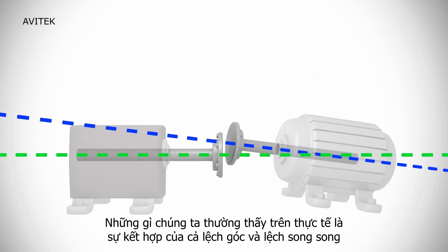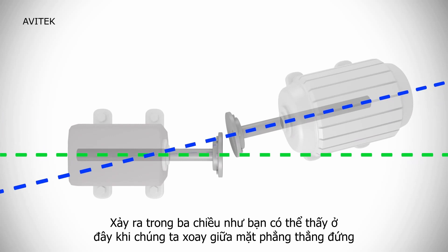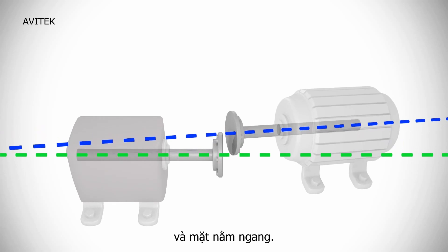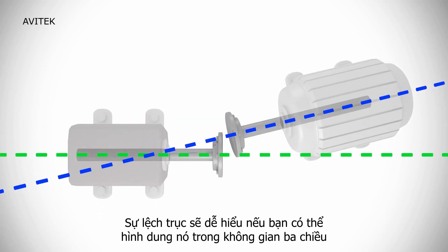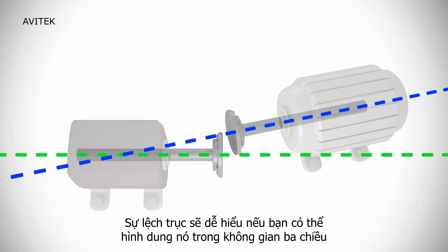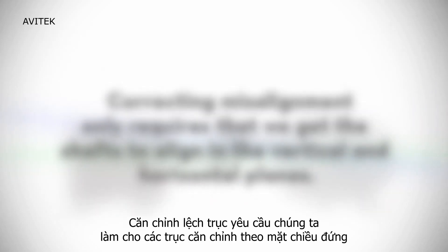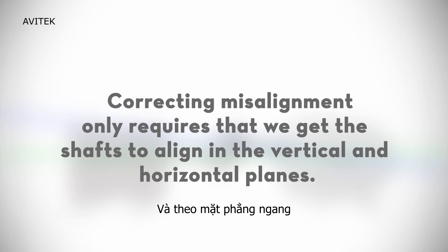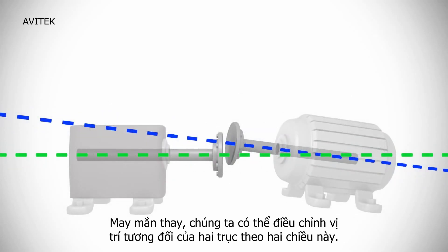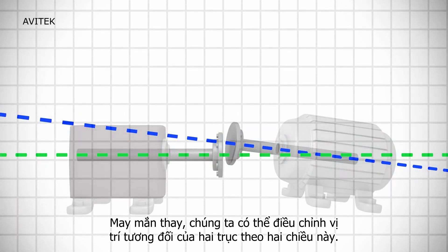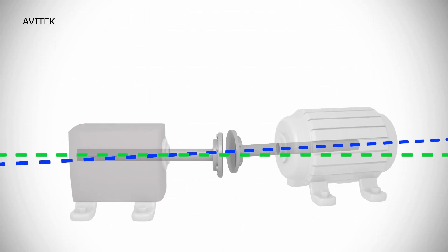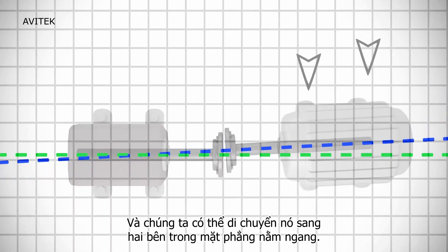What we usually see in the field is a combination of both offset and angular misalignment, occurring in three dimensions, as you can see here as we rotate between the vertical plane and the horizontal plane. While it is much easier to understand misalignment if you can visualize it in three-dimensional space, correcting misalignment only requires that we get the shafts to align in the vertical plane and in the horizontal plane. Fortunately, we are able to adjust the relative position of the two shafts in these two dimensions. We can raise and lower the movable machine in the vertical plane, and we can move it side to side in the horizontal plane.